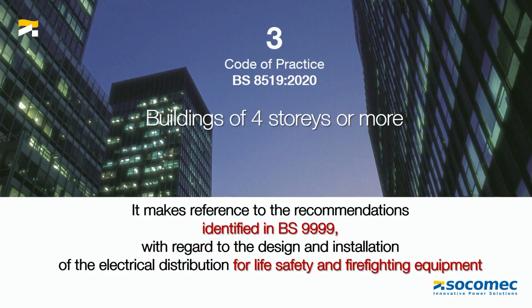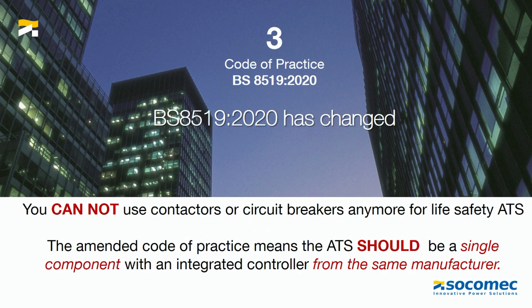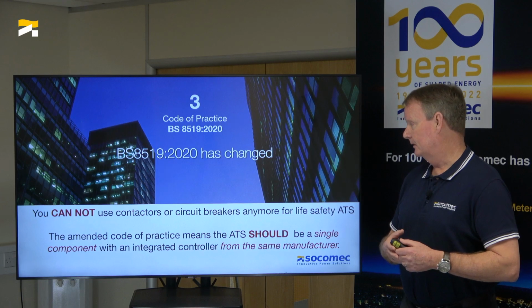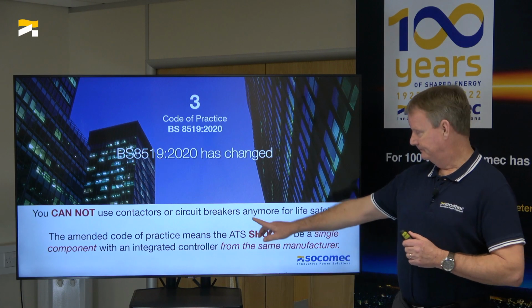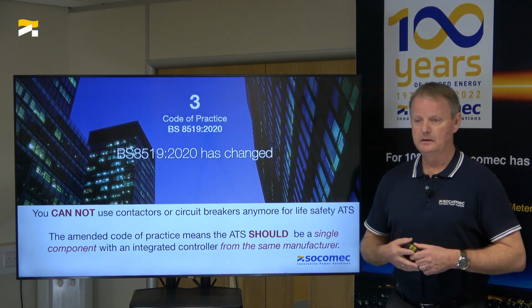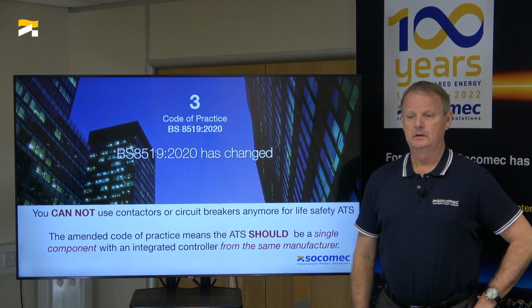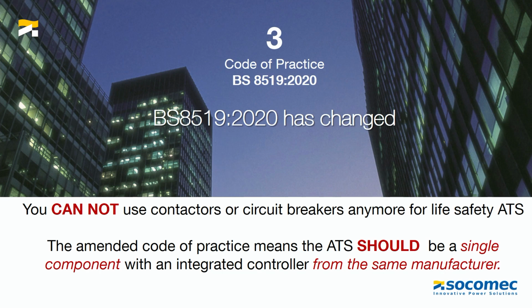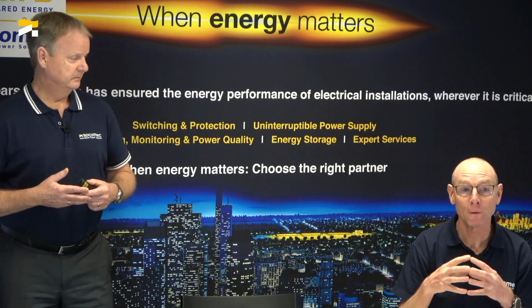So it's identified in BS 9999, and it's changed—unfortunately in the middle of the worst possible time, during COVID lockdown—to the 2020 version. The main point is that you can't use circuit breakers anymore; it has to be a single integrated part, meaning the controller and the switch must be a single integrated unit from the same manufacturer. It's a major change, and I'm afraid it's still not fully understood in the industry.